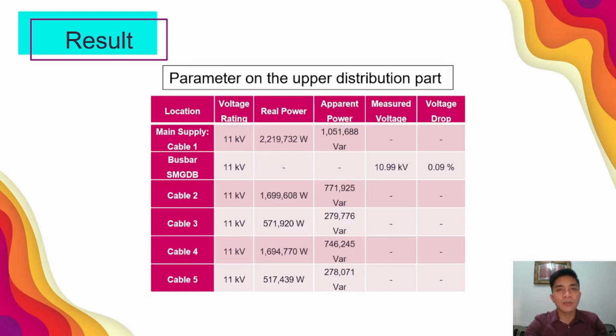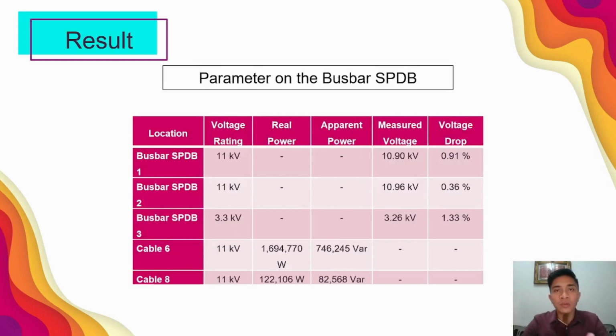So the reading of the busbar SMGDB is 10.99 kV, which has a voltage drop of around 0.09% only. So this is considered a good design as the voltage drop percentage is less than 10%. Okay, moving on to the reading of the SPDB 1, 2 and 3. The voltage reading for SPDB 1 and 2 is still 11 kV, but for SPDB 3 it dropped to 3.3 kV because of the step down transformer from 11 kV to 3.3 kV. So the measured voltage at the busbar SPDB 1, 2 and 3 is 10.9 kV, 10.96 kV and 3.26 kV respectively. So the voltage drop at the busbar SPDB 1 and 2 is less than 1%, while the voltage drop at the busbar SPDB 3 is 1.33% only.